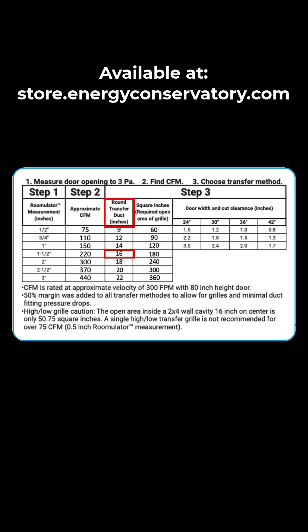Step 3 gives us three options for a passive transfer method: we can use a round transfer duct, a through-wall transfer grill, or we can increase the door undercut. Because the CFM quantity is too high, door undercut is not a reasonable option.